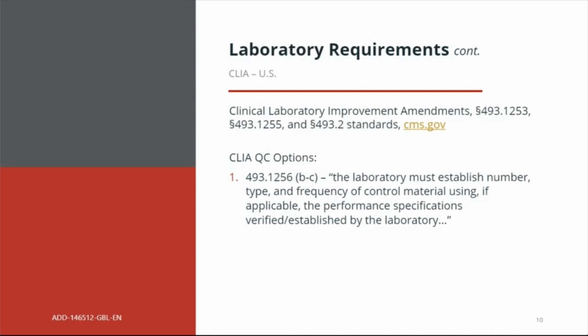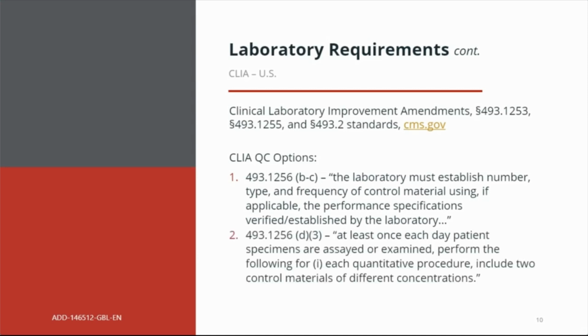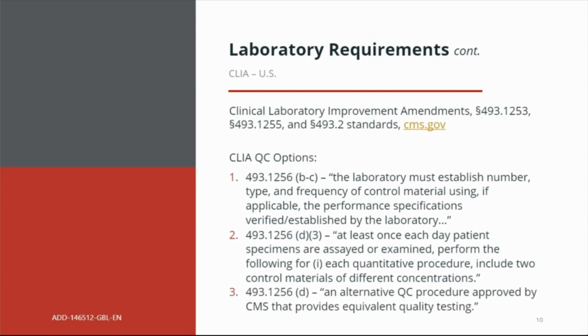The second approach states that at least each day of patient testing that specimens are assayed or examined, the laboratory perform testing utilizing 2 control materials of different concentrations. In my experience, this is the simplest and typically the default strategy employed. It is CLIA minimum. The last option, which was introduced in 2013, is CMS's individualized quality control plan. This plan is a bit more robust. It consists of an evaluation of a risk assessment, a quality control plan, a quality assessment program, and it's intended to cover the entire test process, meaning the pre-analytical, analytical, and post-analytical test phases.